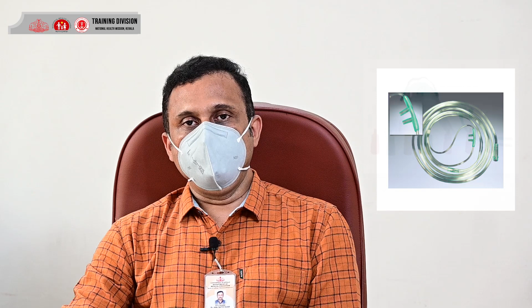Remember that also. Coming to the second major heading, oxygen delivery devices are classified into variable performance and fixed performance, based on whether they provide the peak inspiratory flow rate for the patient. Our simple face mask and nasal cannula are variable performance, because if the patient's rate increases, the inspiratory time decreases and he needs more flow, which is not being given. So we give a minimum of 5 liters per minute in the simple face mask, and he will entrain whatever extra he needs above that 5 liters from the atmosphere. Depending on many factors, the final FiO2, the fraction of oxygen in inspired air, that the patient gets would vary, so it's called variable performance.